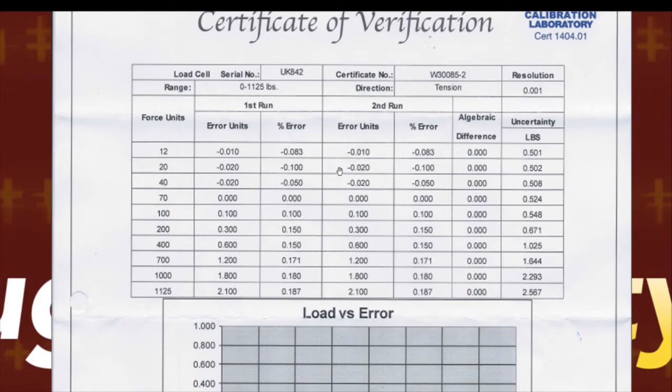He did a series of them, so he's also showing repeatability on his own form, not this one. Yeah, not on this one. On his own form, we don't have a picture of that. Okay, but he did a repetition at 5 and at 6 and at 7, and he used calibrated weights. He checked them on a calibrated scale. He did his homework right.